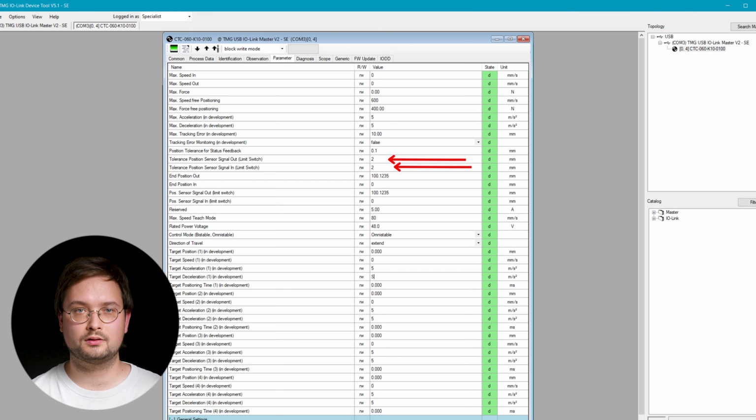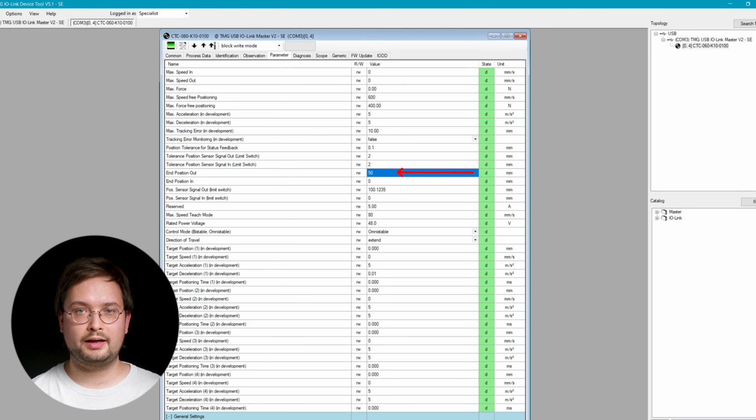Here, in addition to teaching the stroke via user mode 2, we can set the stroke to 100.3 millimeters, for example. We can also set the stroke to be only 50 millimeters. Using the free positioning, you can never go beyond the stroke that is in here. So I can't approach 60 millimeters, but only 50 millimeters.